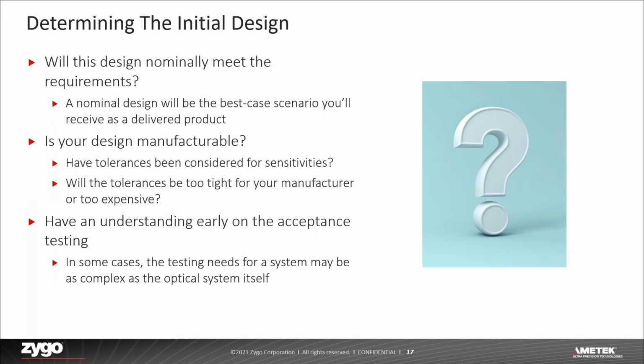When looking at the optical design of your medical device, you first need to make sure that your design meets requirements. It's key to understand that the nominal design will almost always have the best performance you can achieve. Leaving margin on requirements will allow a finished system to achieve the necessary performance. It's also important to start looking at the acceptance testing early. In some cases, designing and building a test bench may be more difficult and complex than the optical system itself. Starting this process early on will help to reduce schedule slips.